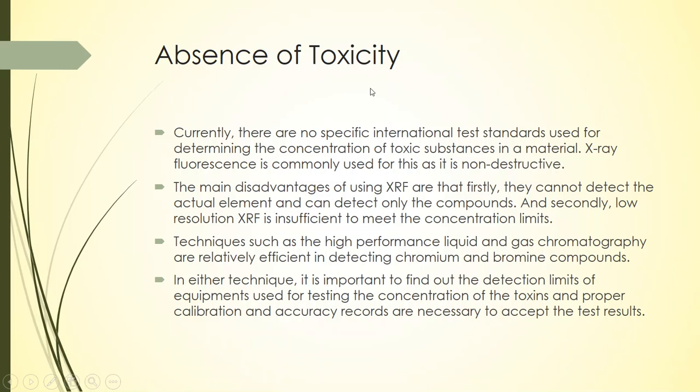Also, the equipment that you're using to detect the limits should be calibrated on a routine basis, and it should have the calibration and accuracy record, which along with the test results should be submitted to the notifying body.